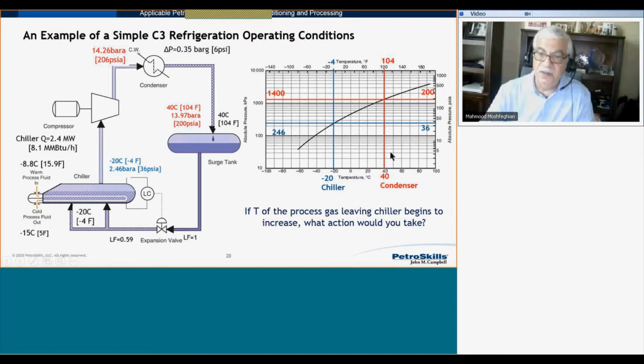Because if I lower the pressure, say from 36, say if I lower it to this value here, then if I lower it to that low value, it's less than -40, that's not possible. So hopefully I can lower the pressure from say 36 to say 30, and 30 gives me a lower temperature of say -28 or so. So if my process gas temperature goes up, the way to correct it is to lower the pressure of the chiller, for example.